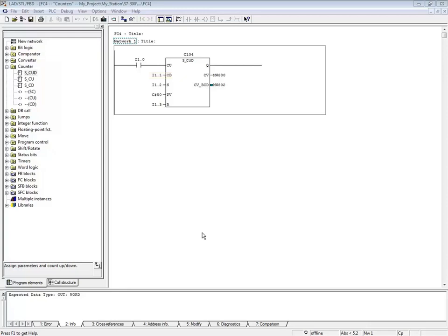is greater than 0. The counter cannot count down if the output is 0, and the counter does not count negative. When the S input, I1.2, transitions from 0 to 1, the preset value, in this example 50, will be placed at the output. The preset value must be formatted with a C-pound before a number, and the numeric range is between 1 and 999.